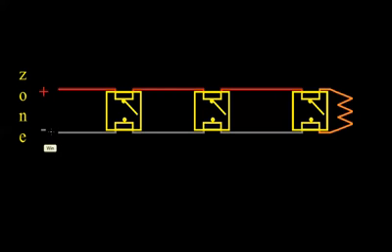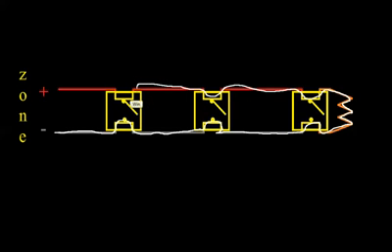This is a conventional zone, and we know that they use current monitoring to detect either complete circuits, open circuits, or alarms. They do that by using an end-of-line resistor that limits the current on the circuit. So we have a certain amount of voltage, usually around 24, at the front of the zone, and then we have all our normally open devices, and at the end we have this resistor. The current can't go through any of the devices because they're normally open, so it flows through this resistor, which limits how much current can flow, and the panel detects that as a complete circuit.